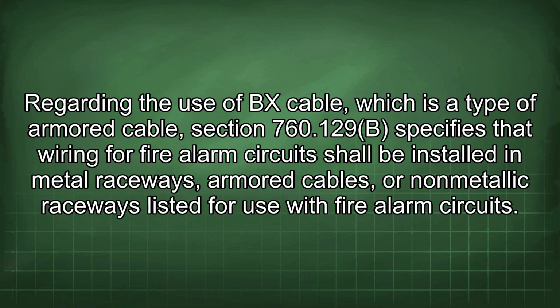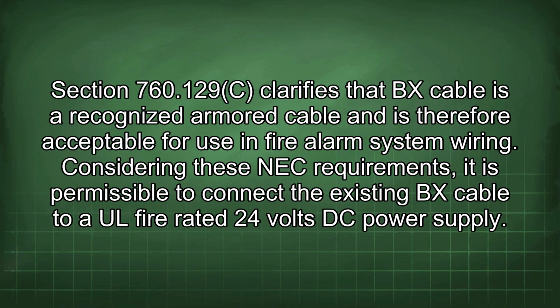Regarding the use of BX cable, which is a type of armored cable, Section 760.129b specifies that wiring for fire alarm circuits shall be installed in metal raceways, armored cables, or non-metallic raceways listed for use with fire alarm circuits. Section 760.129c clarifies that BX cable is a recognized armored cable and is therefore acceptable for use in fire alarm system wiring.